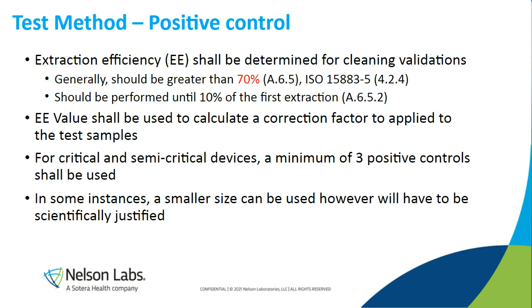However, in some instances, a smaller size can be used, but it will have to be scientifically justified. I'm sure you've seen this language in many, many documents. It's a common language that you see. And when would be a case where you would justify this? From my perspective, when I read this, I would think that it would be for non-critical devices, devices that require low-level disinfection that are non-patient contacting devices, keyboards, iPads, things that are in the OR room or in a clinical setting where they are not touching the patient, but we are still doing reprocessing instructions for them. In that case, it could be justified that you can do 1 positive control because it is non-patient contacting. The risk of infection is very low, and also we don't need to worry about doing so many controls because the test soil accumulation over time is not there.